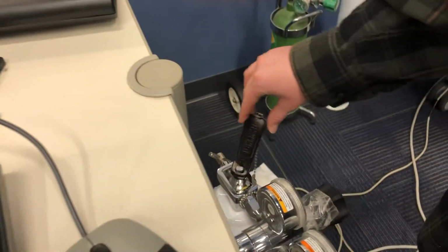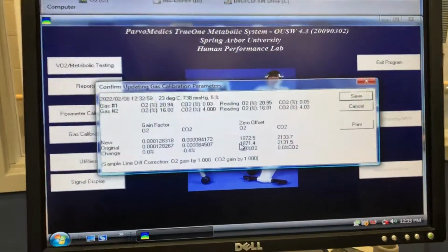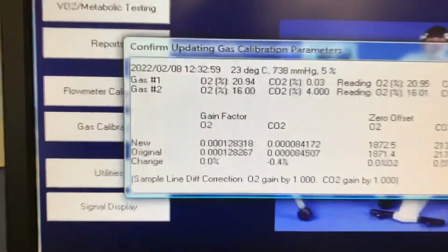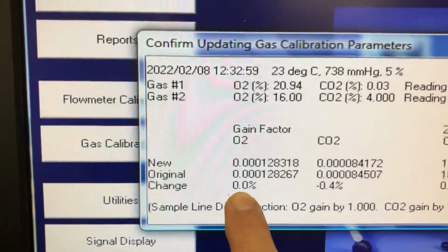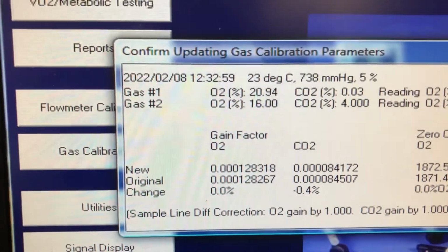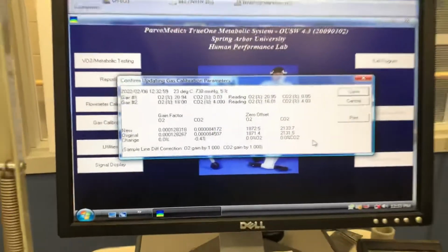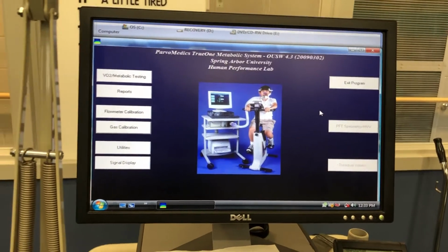We turn the gas off, back to the 3 o'clock position, come up here and hit OK. We can see our numbers here: we're at 0 and we're at -0.4, which is still less than 3%, so we should have a good calibration. We hit save, and we shouldn't have any warnings. Fantastic.